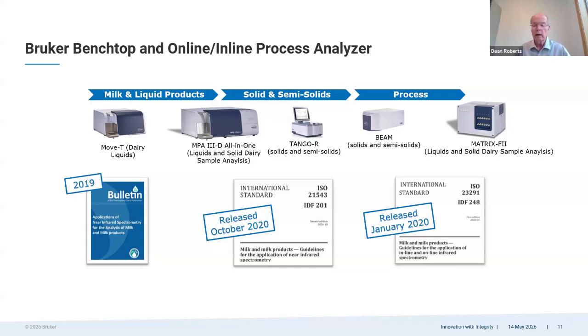And the flow cells are made from quartz, which does not wear over time, which eliminates drift. So moving from the left to the right, we've got the MOVE-T dairy analyzer, which is dedicated for liquids. We've got the MPA3 dairy analyzer, which is a hybrid system that can measure both solids, cultured products, powders, and the fluid dairy products. The Tango R is a benchtop instrument that operates in reflection, and that is used to measure powders or cultured products or cheese products and other solids.